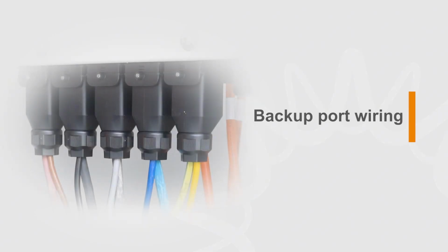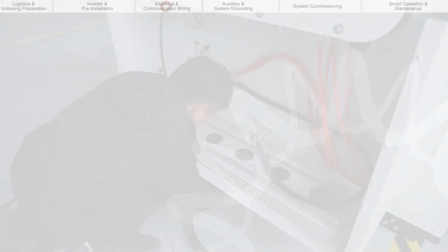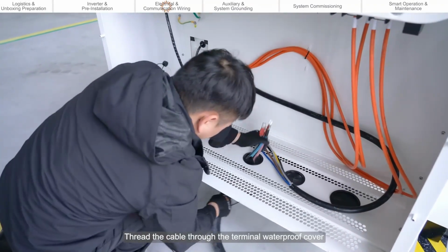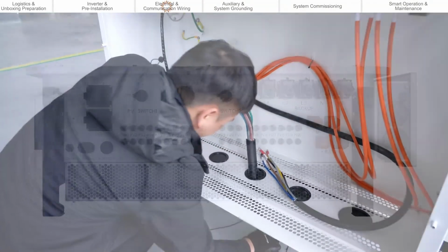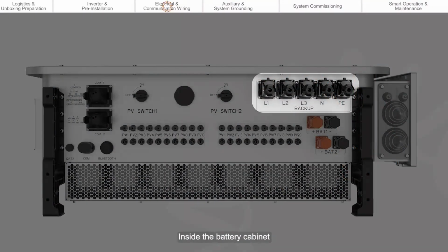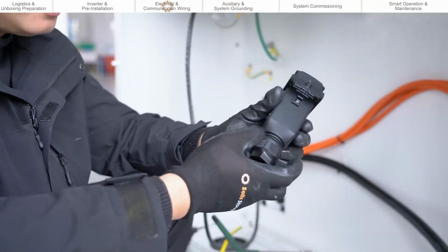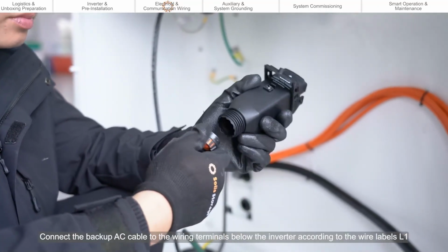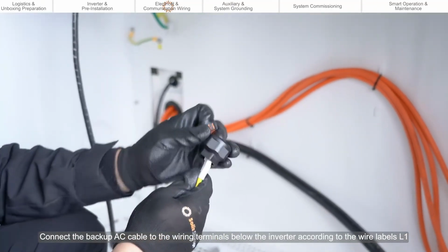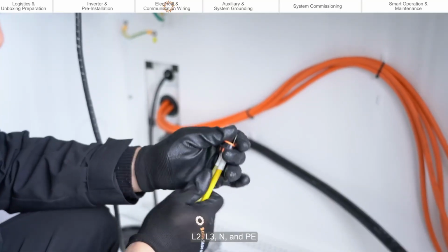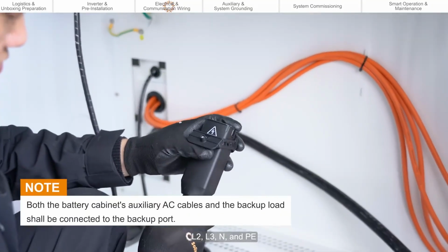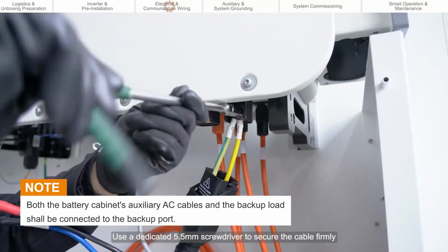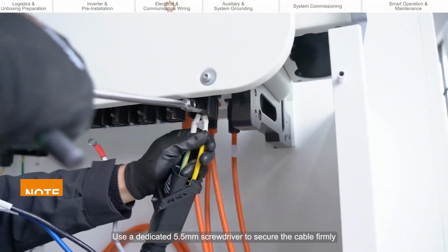Backup port wiring. Thread the cable through the terminal waterproof cover. Inside the battery cabinet, locate the backup cable. Connect the backup AC cable to the wiring terminals below the inverter according to the wire labels L1, L2, L3, and N. Use a dedicated 5.5 mm screwdriver to secure the cable firmly.